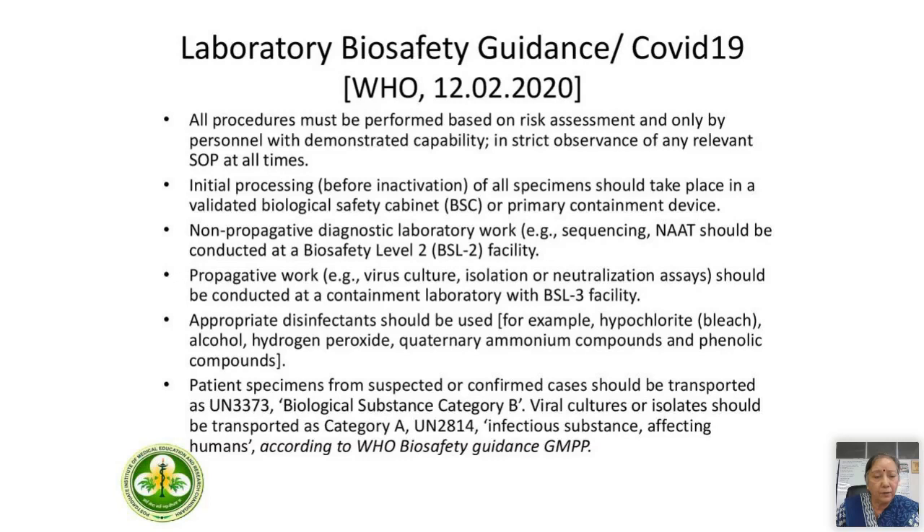Initial processing before inactivation of the virus should be done in a validated biological safety cabinet or primary containment device. Non-propagative diagnostic laboratory work, which includes sequencing and NAAT, should be conducted at a biosafety level 2 facility. Propagative work — including viral culture, isolation, or neutralization assays — should be conducted at a containment laboratory with BSL-3 facility.